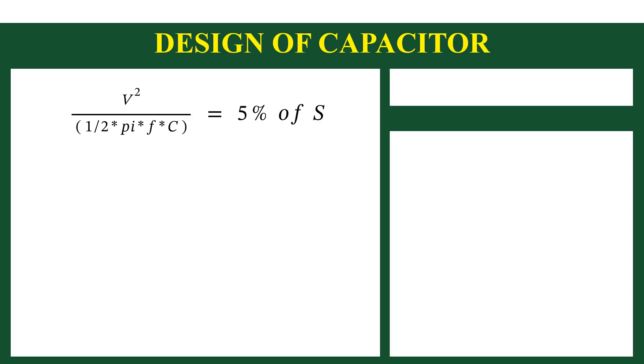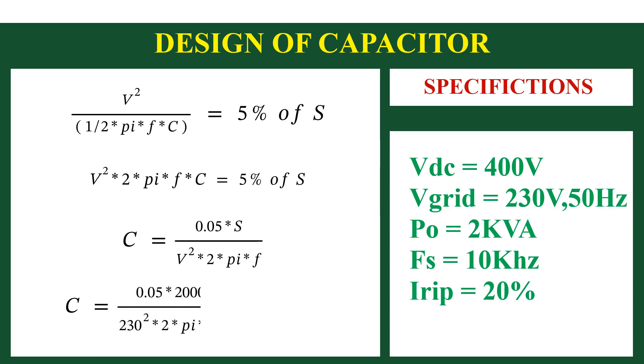This can be rewritten as V square into 2 pi fc is equal to 5% of S. Therefore, C is equal to 0.05 into S divided by V square into 2 pi f. Now substitute the values from the given specification. We will get value of capacitance as 6.01 micro farad.